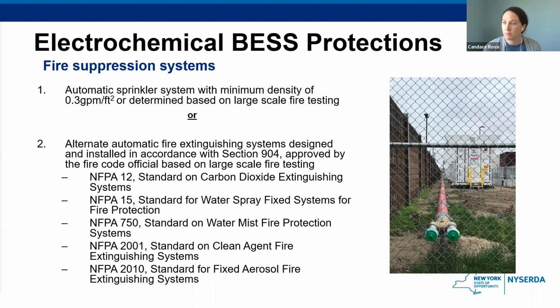This is the fire suppression system requirement. This is necessary as a containment response to any thermal runaway or other issues in the system. These systems can be set up as a sprinkler water system or usually a clean agent-based system. There's the automatic sprinkler system that requires the minimum water density as you see there, or whatever is determined based on large-scale fire testing. Although the code calls out this water density, there may be a challenge to get that much water density to upper floors of a high rise or an area that does not have good water pressure.